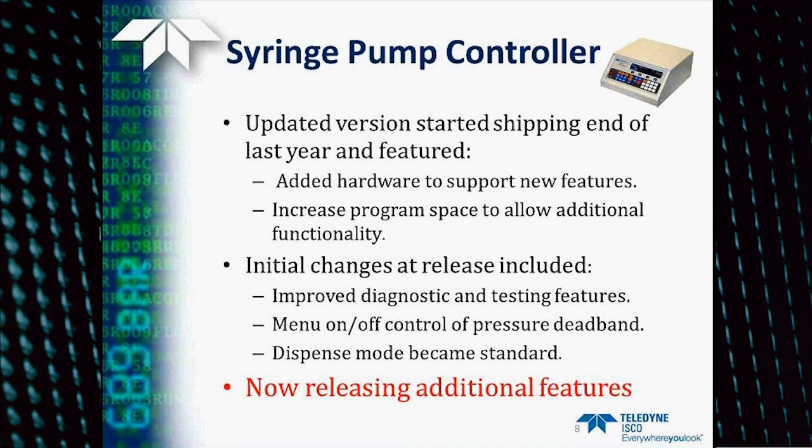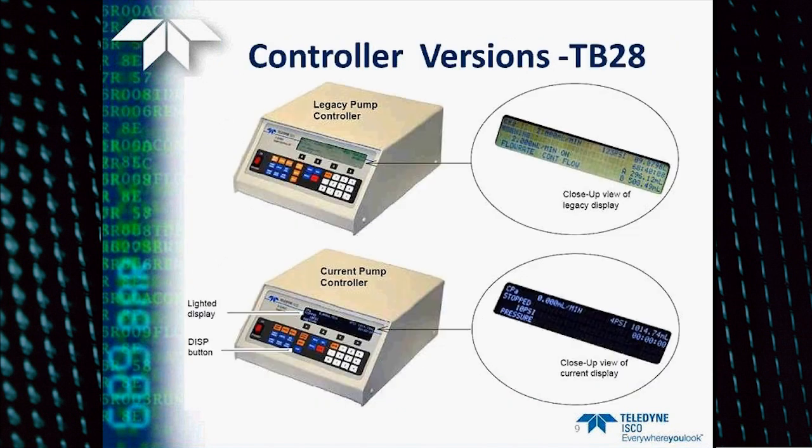Initial changes that we released with this controller were some improved diagnostic and testing functions, a menu on-off control of pressure deadband in constant pressure, and a dispense mode, which had been optional, became standard in this software. And now we've just released some additional features for the pump.